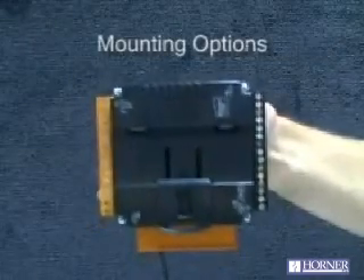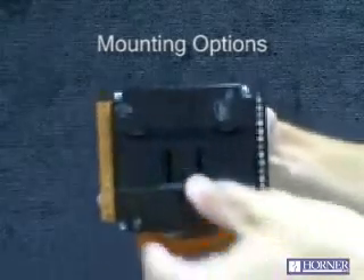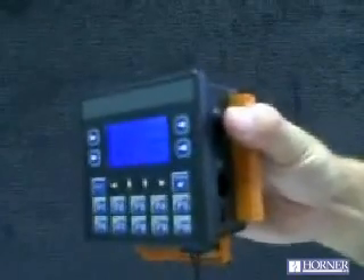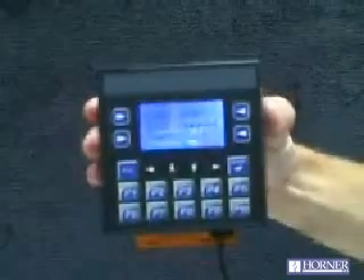The XLE can be mounted in two different fashions. It can be mounted inside your panel on DIN rail, as you can see from this built-in mechanism with a locking clip. It can also be mounted as a traditional operating interface on the door of your panel. When it is, its quarter-DIN cutout — which is a standard punch size — allows it to be completely watertight and good for NEMA 4X ratings.